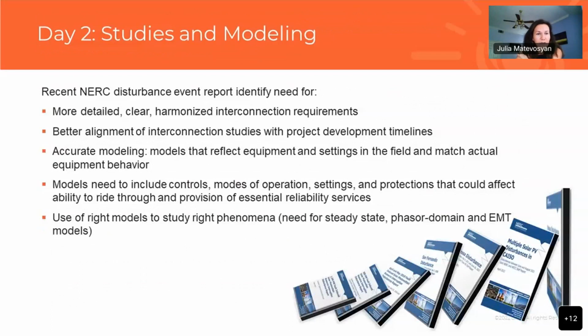that have happened recently and NERC analyzed. So all of them identify need for more detailed, clear, harmonized interconnection requirements, better alignment of interconnection studies with project development timelines, accurate modeling, and we need models that reflect equipment and settings in the field and match actual equipment behavior. Models need to include controls, modes of operation, settings, and protection that could affect ability to ride through different disturbances, and also indicate provision of essential reliability services.